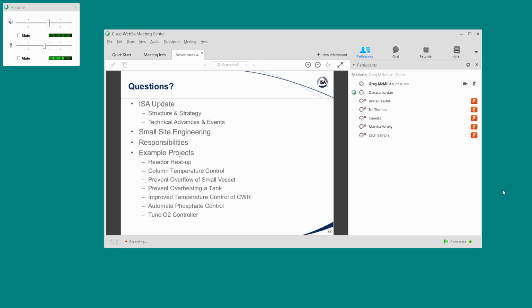Well, one thing I'd like to note is that when you're between the output limit and the anti-reset windup limit, my understanding is the reset time is 16 times smaller, so you get 16 times more integral action, and in a few cases that's useful, but in most cases that's just way too much integral action going on.